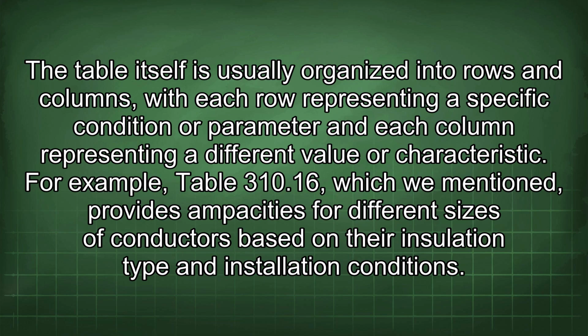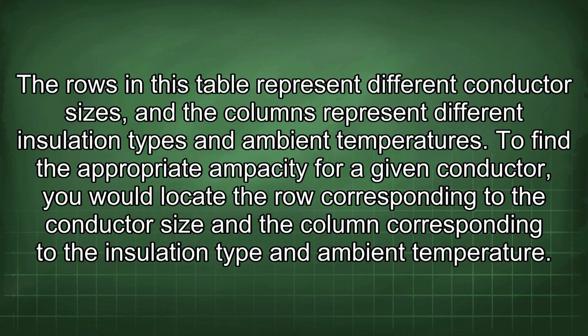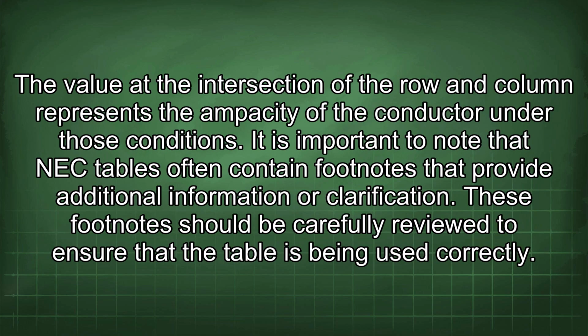For example, Table 310.16, which we mentioned, provides ampacities for different sizes of conductors based on their insulation type and installation conditions. The rows in this table represent different conductor sizes, and the columns represent different insulation types and ambient temperatures. To find the appropriate ampacity for a given conductor, you would locate the row corresponding to the conductor size and the column corresponding to the insulation type and ambient temperature. The value at the intersection of the row and column represents the ampacity of the conductor under those conditions.